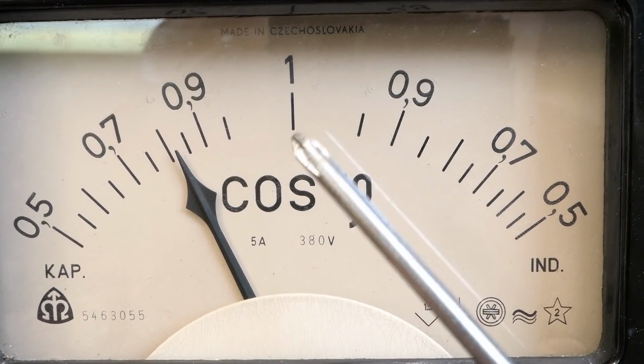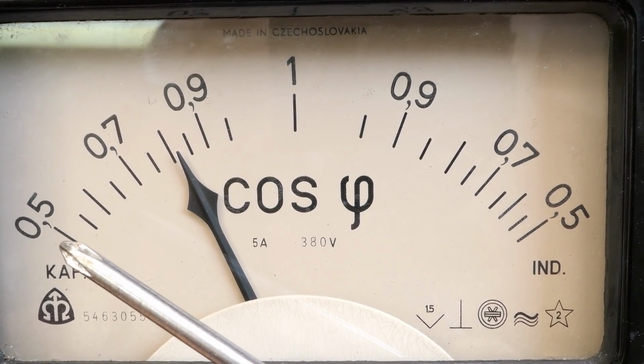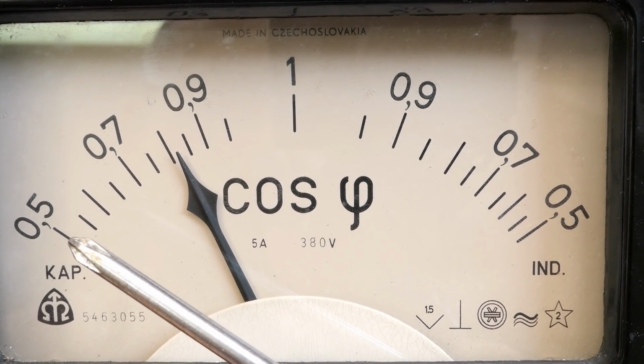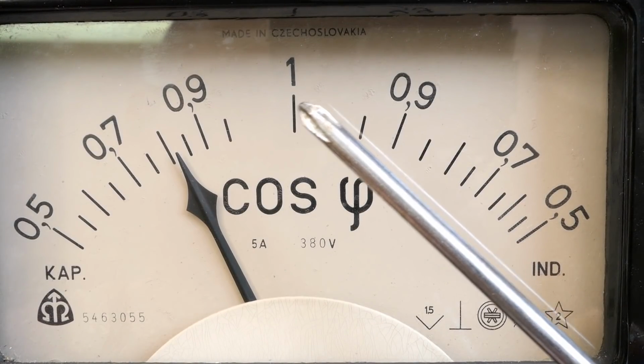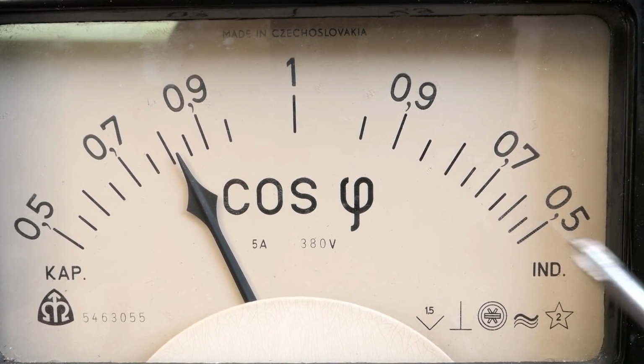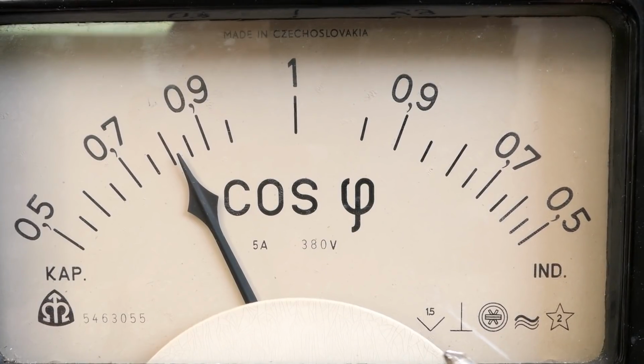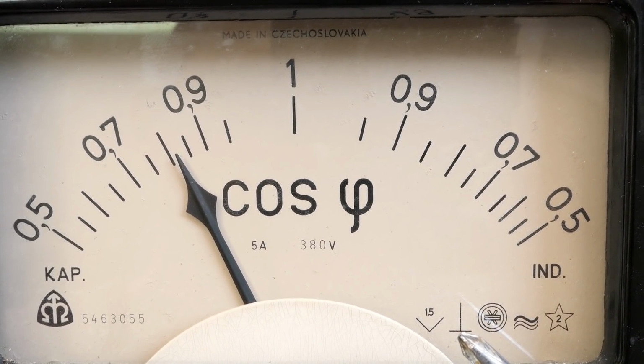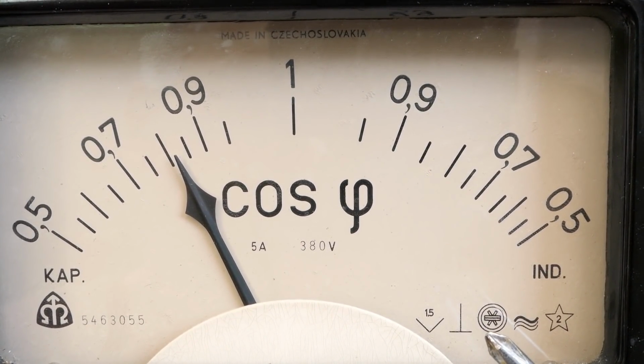Now let's take a look at this power factor meter. It goes from 0.5 power factor capacitive through 1 all the way to 0.5 inductive power factor. And the marking says 1.5% accuracy, vertical operation, and the system is balanced ferrodynamic.